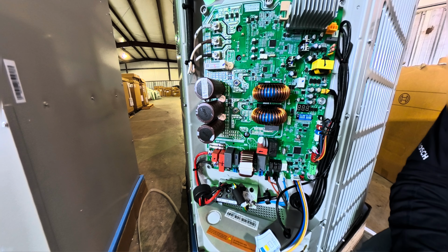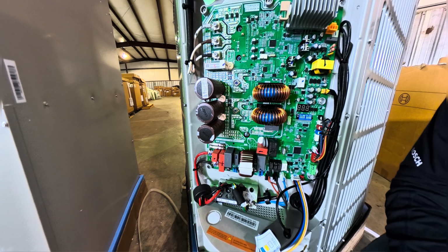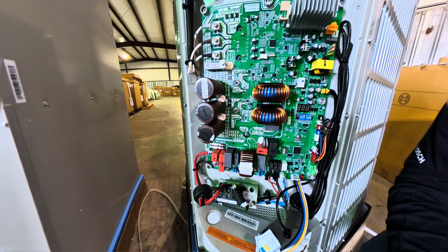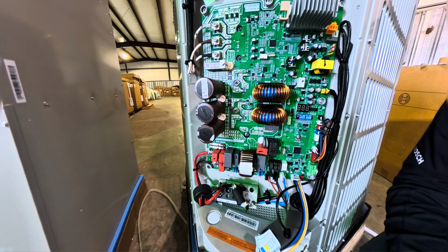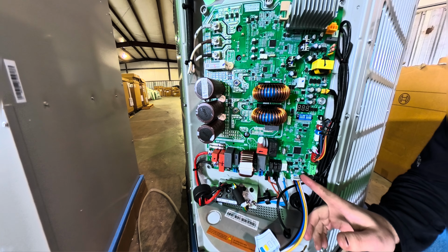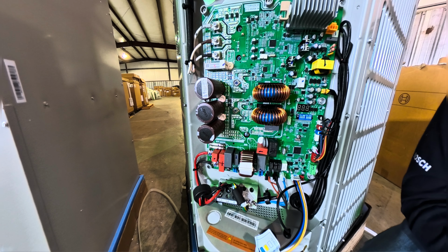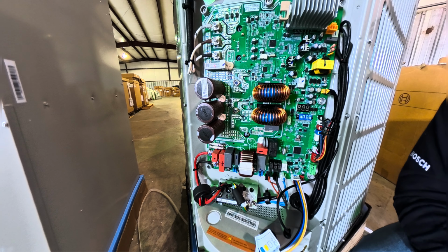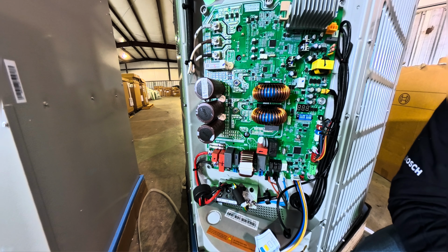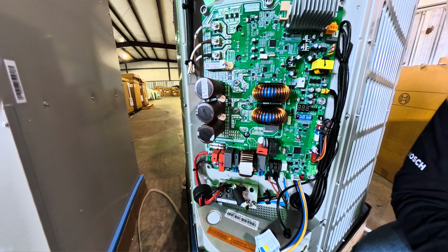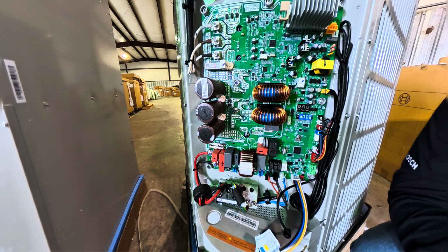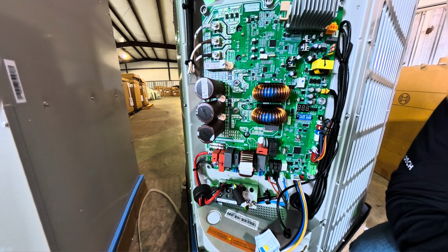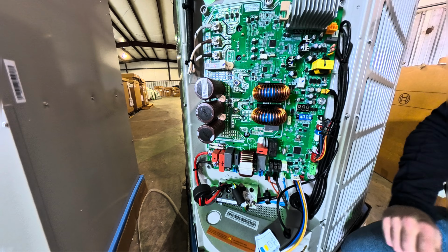If the customer wants an Ecobee or a Honeywell or a Nest, whatever they want, they can use the thermostat they want, the thermostat you like and trust on this unit. You don't have to use a Bosch thermostat if you don't want to. Whether this is wired communicating or not, no matter what, it's still going to be 24-volt wiring between the thermostat and the air handler. So this board's just communicating to the indoor unit. From what I hear down the pipeline, there's also going to be an option to wire a 15 SEER outdoor with a 15 SEER air handler in communication mode if you wanted to as well. Again, that provides a little bit extra dehumidification if needed in the proper application. So that's pretty much the overview of this board.